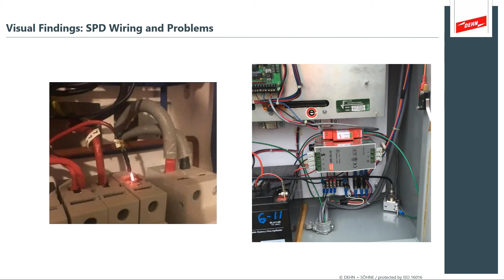So in an electrical panel, something that looks like this, green wire going to this surge protector, green wire for this surge protector, it's sort of like a big loop in there. And that's not actually best practice. It's connected and it works, but when there's a surge event or any sort of other transient that might cause disruption, it causes more havoc than it solves by having all these loops.